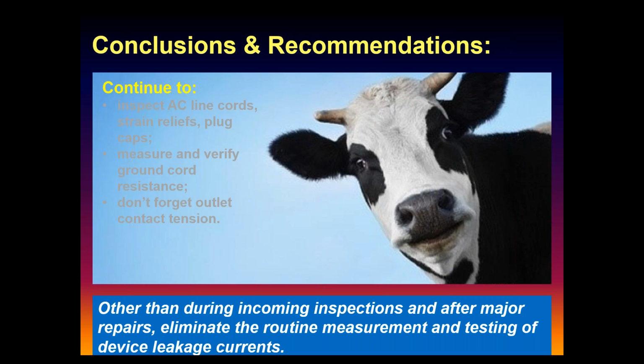So if you connected your multimeter between L1 and ground, for example, with very low resistance, you'd probably read about the same current that you're reading on the isolation monitor. So it's a goofy concept - one that's got us buffaloed in that industry, that whole transformer industry Dr. Noble mentioned earlier, they were pushing this stuff big time. And isolated power made sense when you had flammable anesthetics.